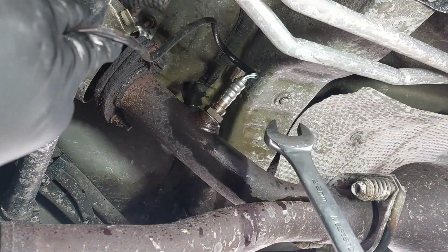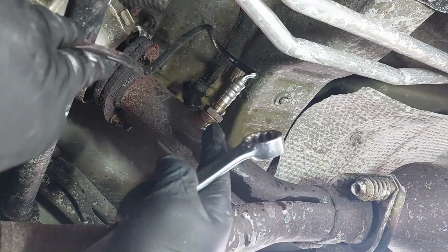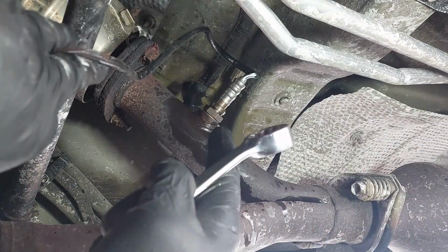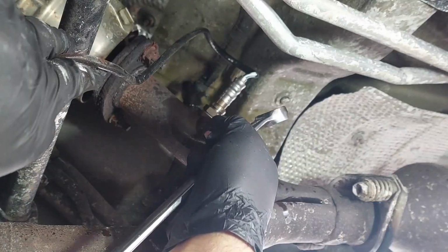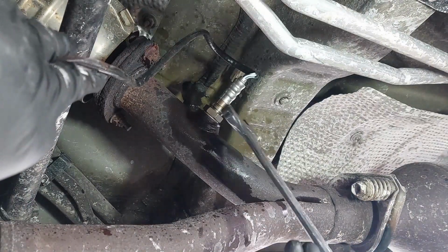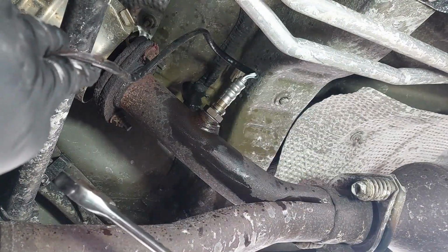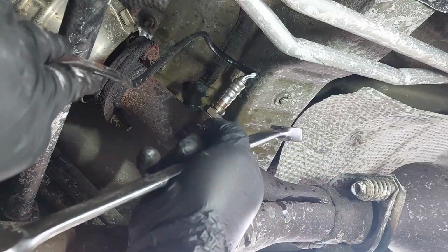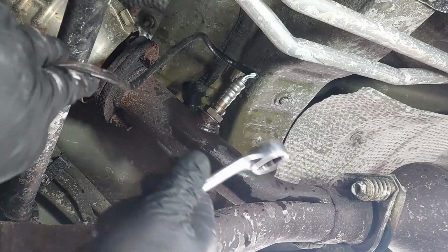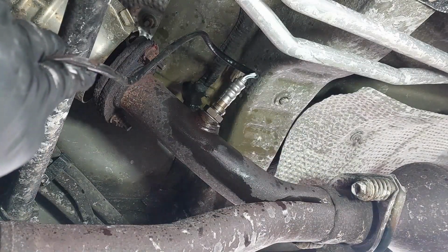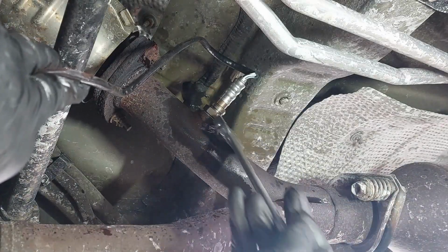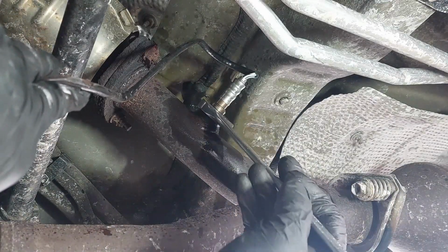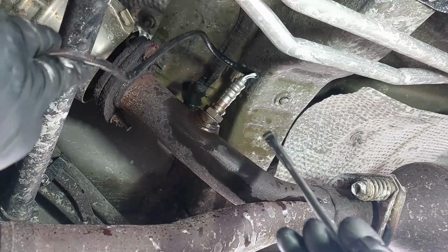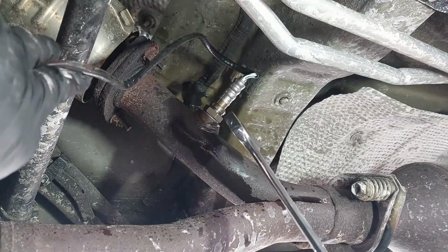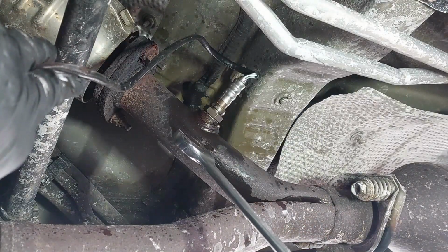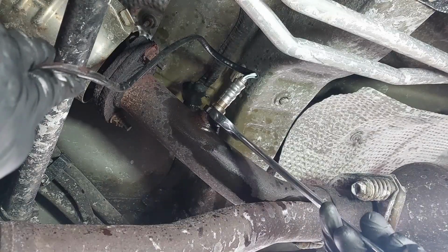You don't want it too tight or too loose, just enough to crush the crush washer gasket that's underneath here. There's a gasket, so you want to make sure that you tighten it just enough to crush that washer to make a perfect seal. There is a torque spec, usually a range. I'll have to check on what the paper manual states that came with the sensor.